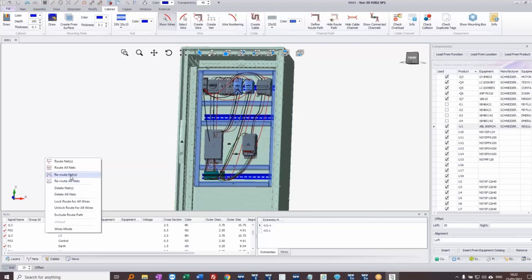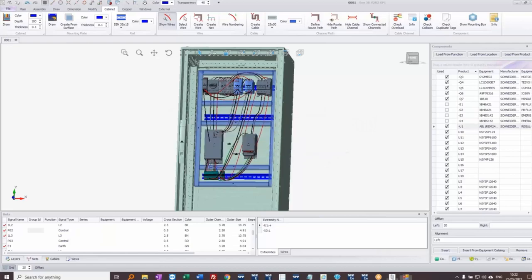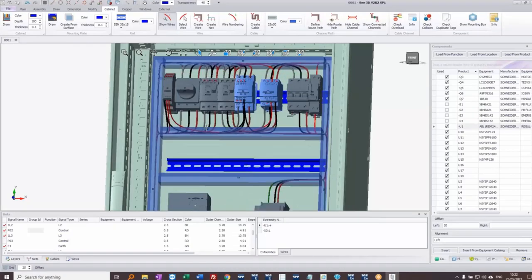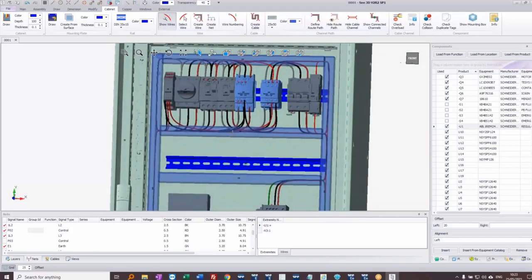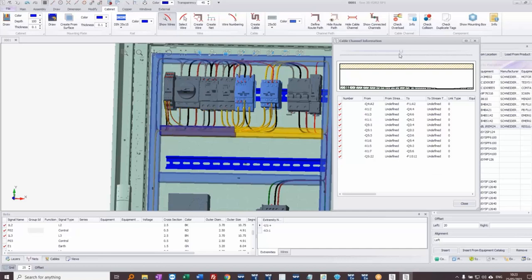Now if I right-click over the wires I can reroute all nets, and I can see them now following the wireways and cableways. I can click on a wireway to see a side view — wireways have a reserved area shown from the top, maybe 20% spare. As I drag the cursor across, a blue bar moves in the background, showing exactly which wires pass through at each point and how much space remains.